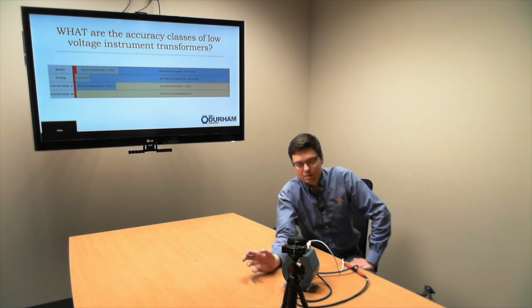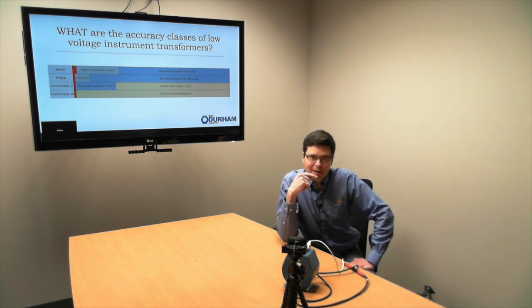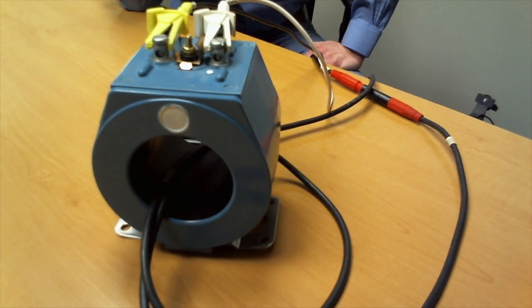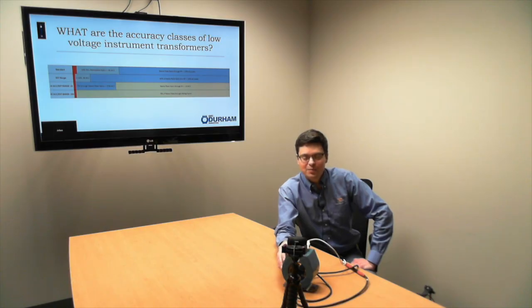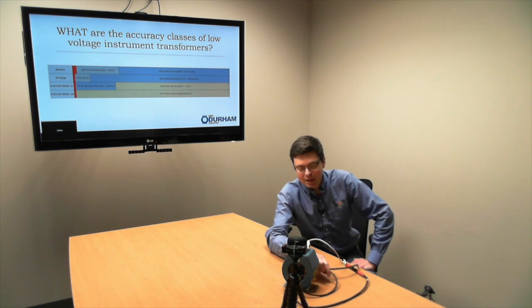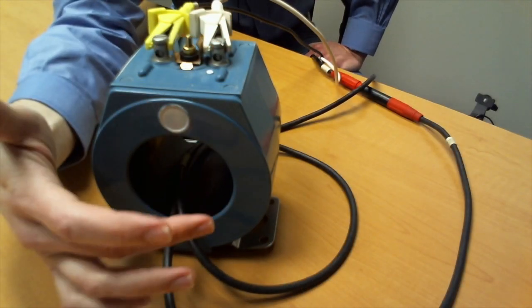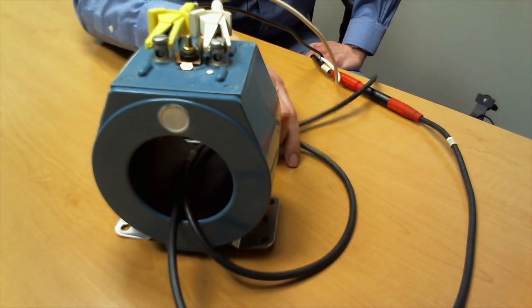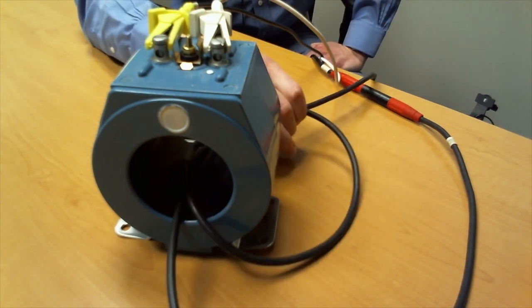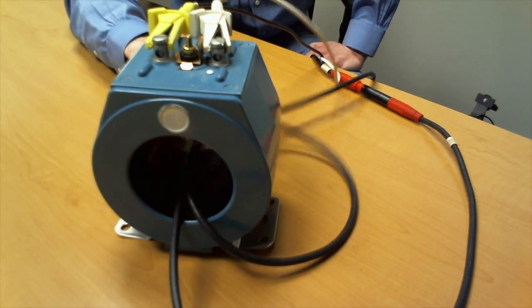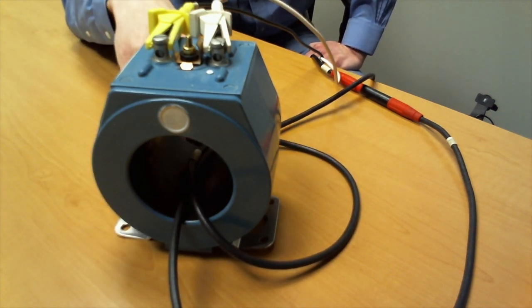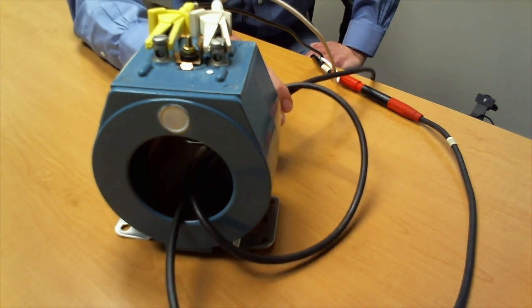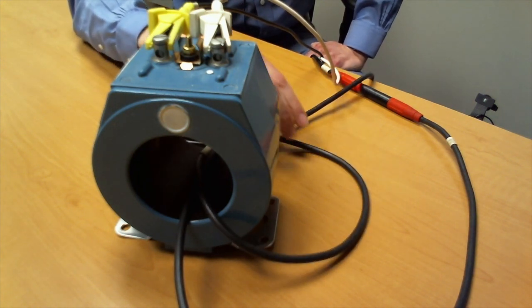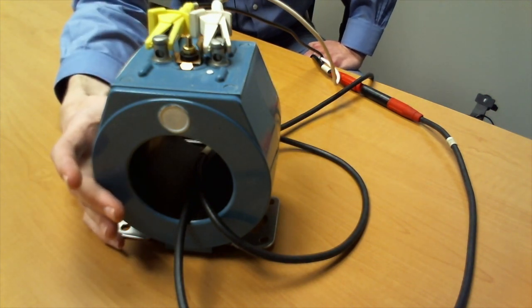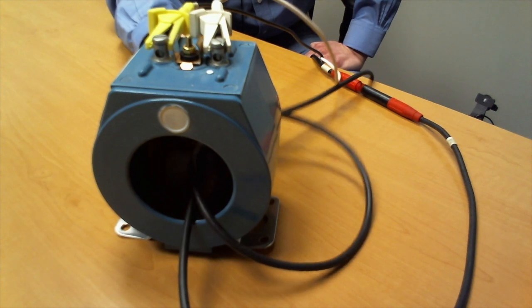So using the PowerMaster 7 series, you can actually buy an accessory called the CT load boost cable. And this is the accessory cable we have here. So if you're looking at the CT, you've got the primary line coming in here. If you see the dot, I'm coming in through the dot side, and I've got 2 loops of this cord going through this transformer. So I'm going to drive the inside of the core of the CT and excite it and get it up to a certain amount. I can wrap this 2, 3, 4 times, as many times as I want. I can get through the window of the CT, and this is a large window, so I've got a lot of ability to wrap it. So I'm going to wrap it 2 times.